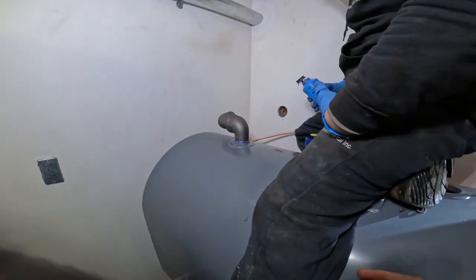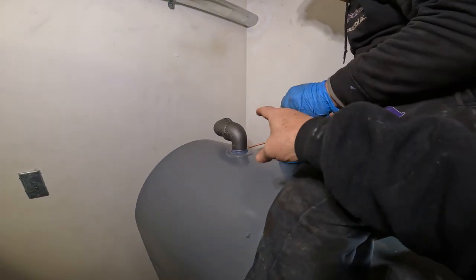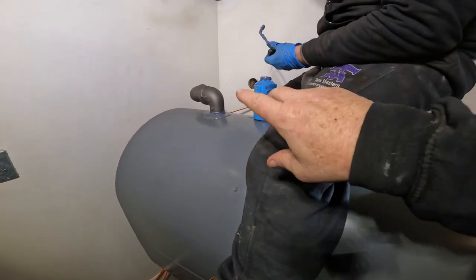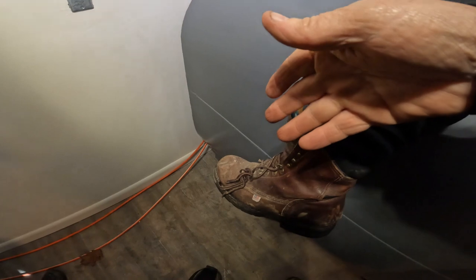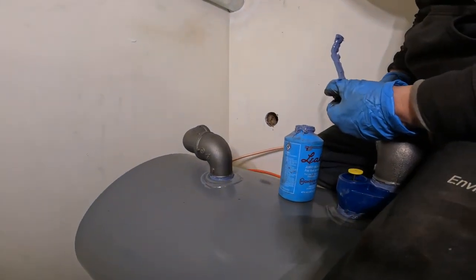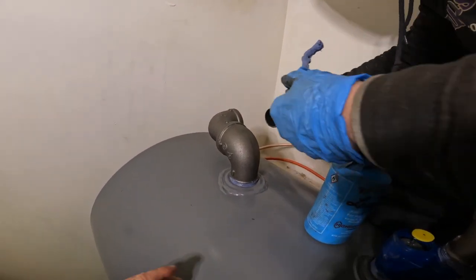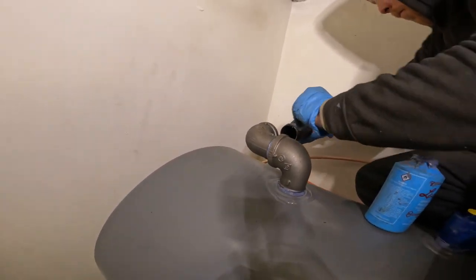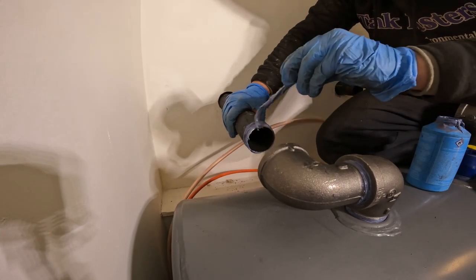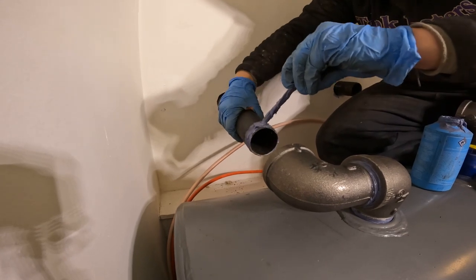Okay, so we're sending through the actual pipe and Craig will thread it. Normally, we'll have that pipe in here and set already with the pitch, and then we just push the whole tank and slide it through the holes. But because we have a wood floor, we have to do it this way, which makes it much more difficult. Go ahead. Send it. It makes it a lot more difficult because this has to be lined up perfectly now. So when he starts to turn it, you don't want to have a cross thread. So Craig is doping it up now.